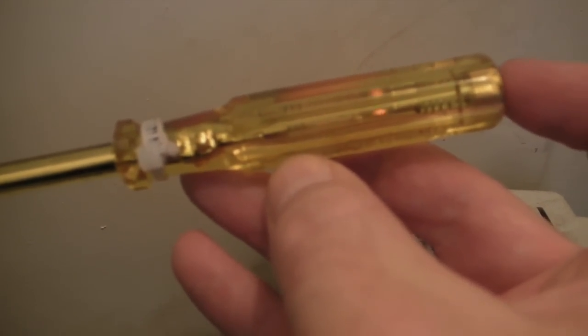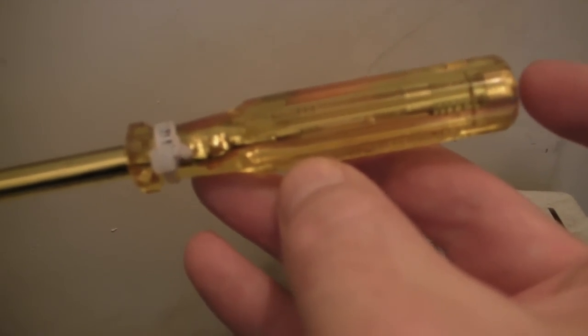Now I'm using this test light. There you go, you can see that's lighting, so that's going into my main feed there. It's coming in via this, somebody's kindly marked this programmer wire. As it comes in this wire, it's fed in there and it goes up via the room thermostat wire, so it's going up via the red wire up to the thermostat, and I know it returns when it's calling for heat back in this yellow wire.